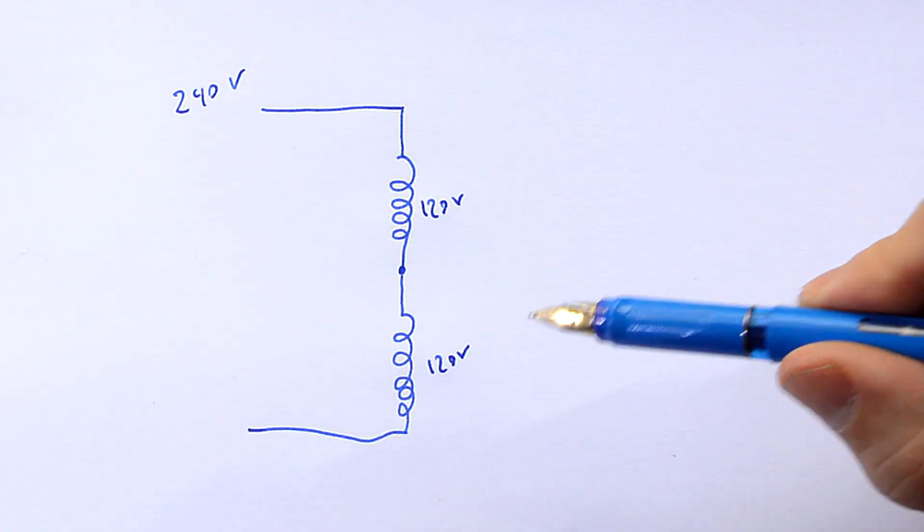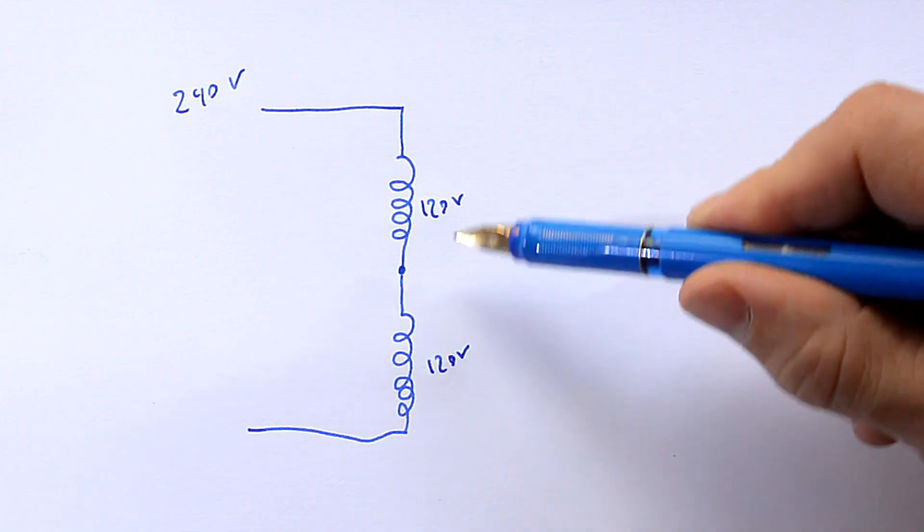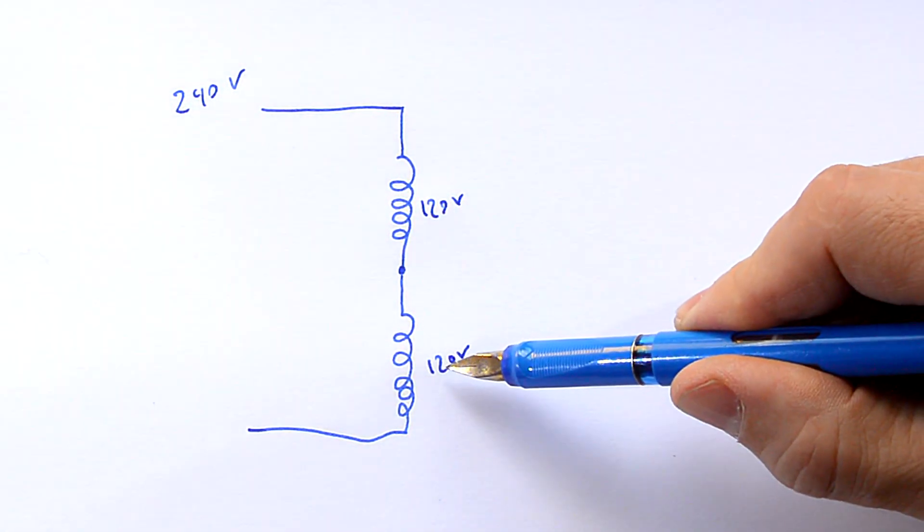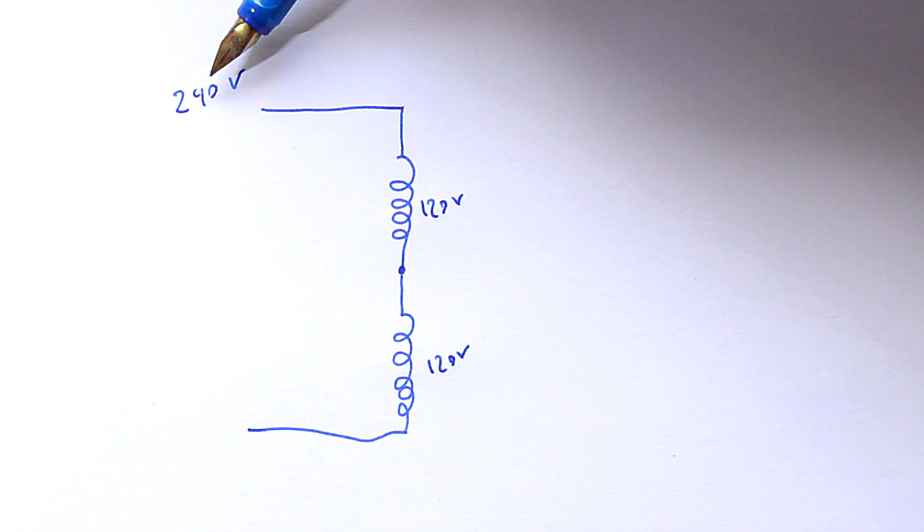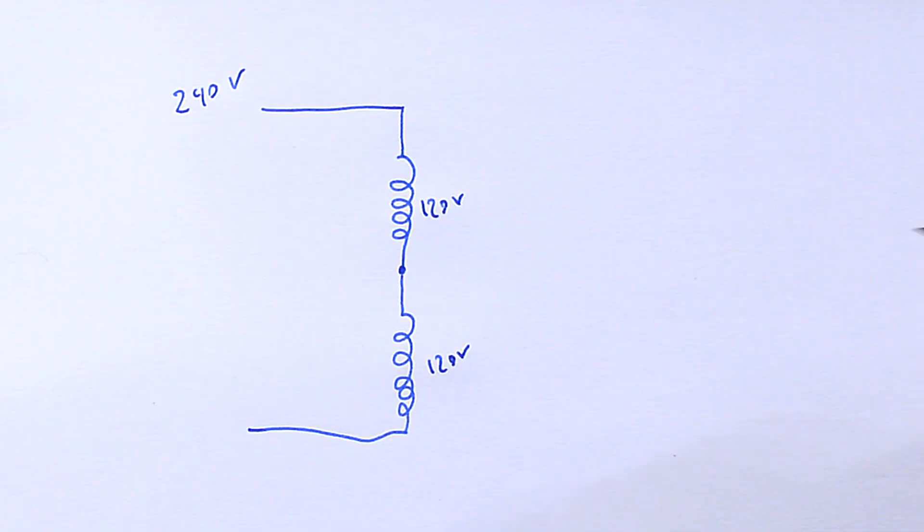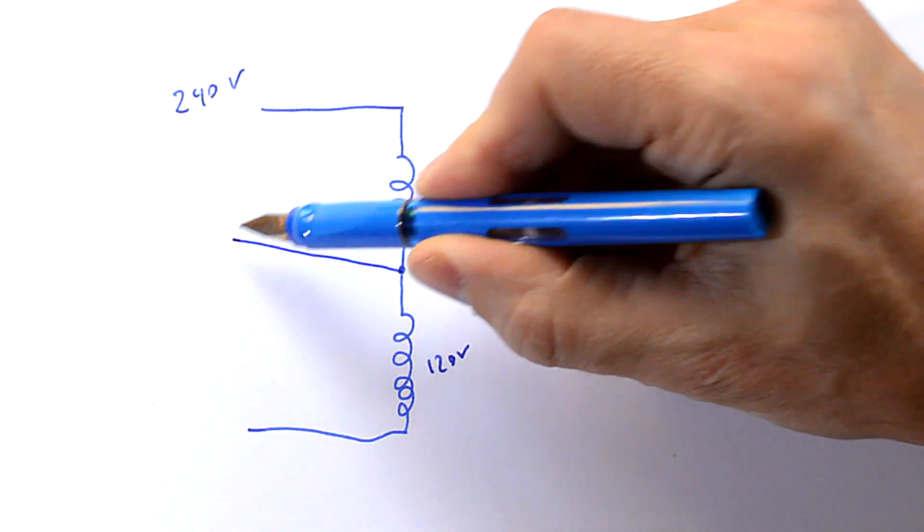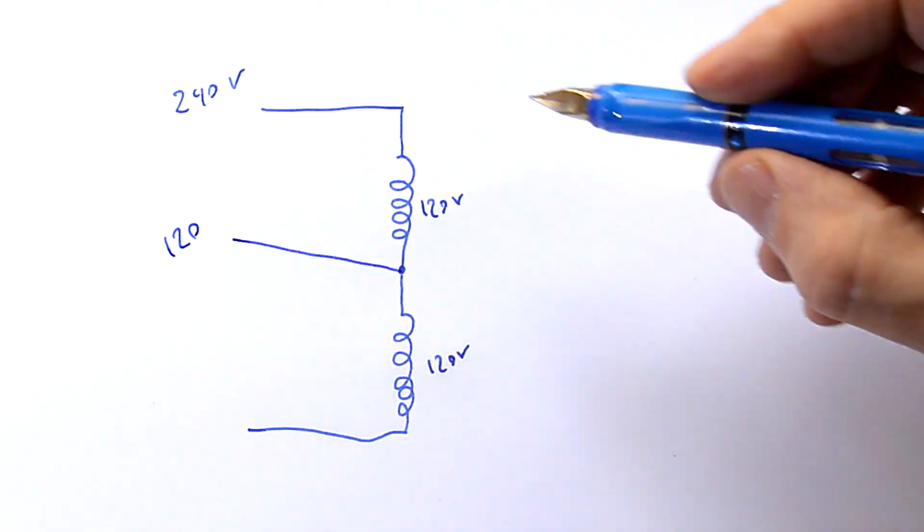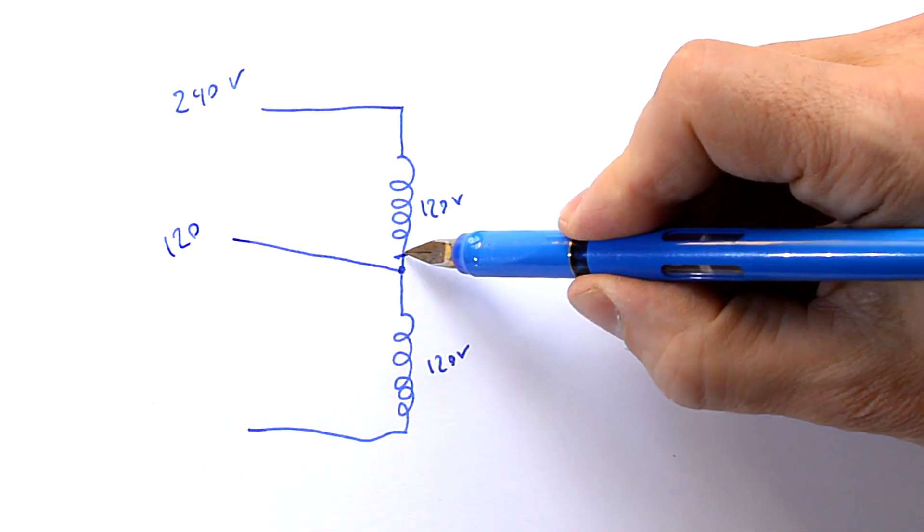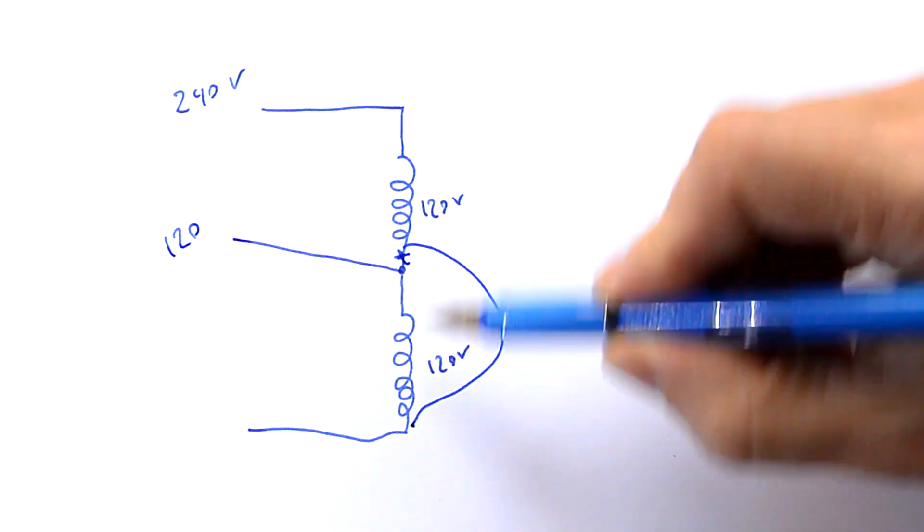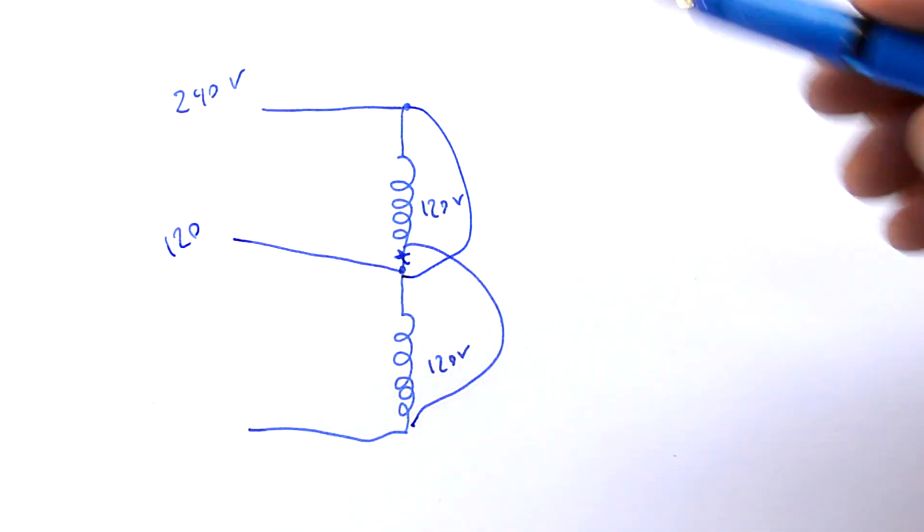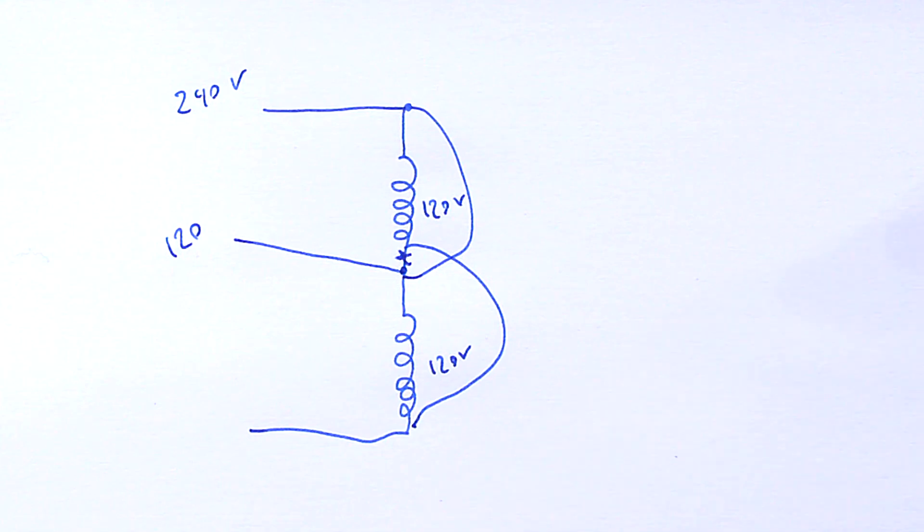The way these dual voltage motors work is you have two 120 volt coils in series and together those get up to 240 volts. Now if you want to run the motor at 120 volts you basically have 120 volts coming in here and you take this coil and rather than having it go here that goes here and that connects here. So effectively you have the 120 volt coils in parallel.